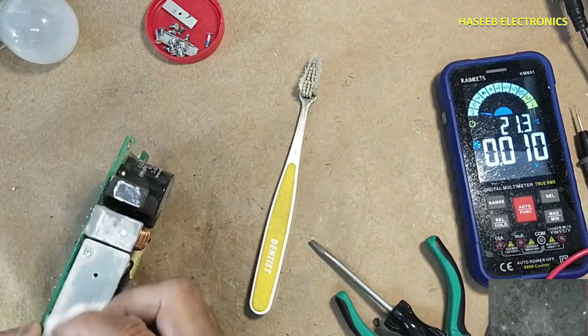Using diode mode, black lead at positive terminal of the bridge rectifier input terminal, and negative terminal. This is wrong, this reading is wrong - it must be open circuit. There is a short circuit on the bridge rectifier terminals.